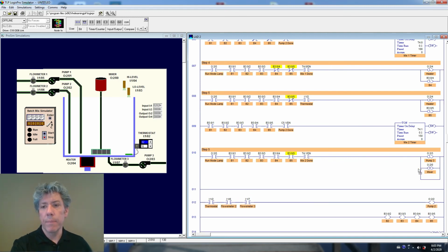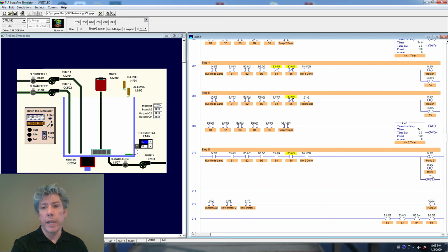Now, how do you do that? Well, there's actually a really nice instruction under timer counters called reset. What it does is it resets whatever you point it at. If I were to put C:1 here, it turns out in this language it wouldn't work quite right. It would actually reset the accumulated value, or the count in that counter, to 1 instead of 0. That's not what I want. I want to reset just the accumulated value. The accumulated value is the count. It's how many events the counter has remembered have occurred. It's this value right here.